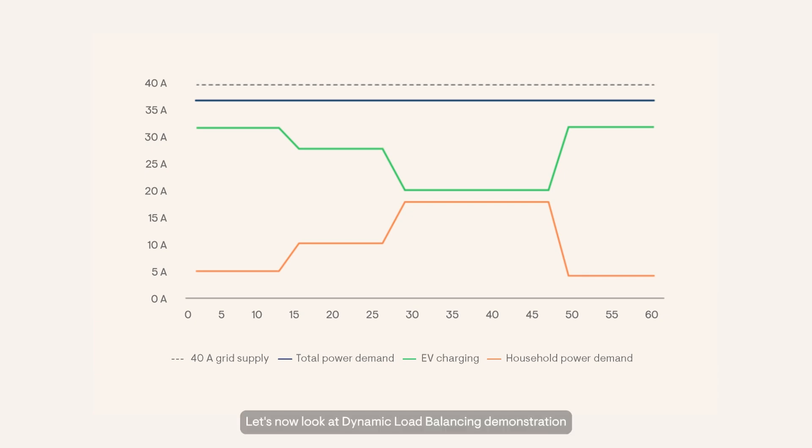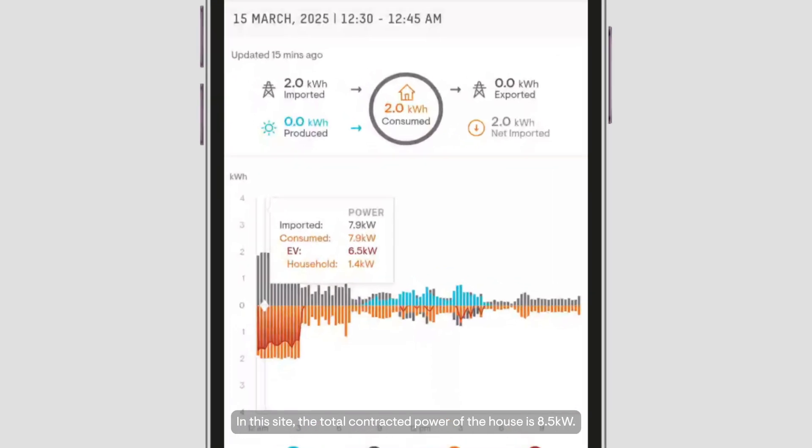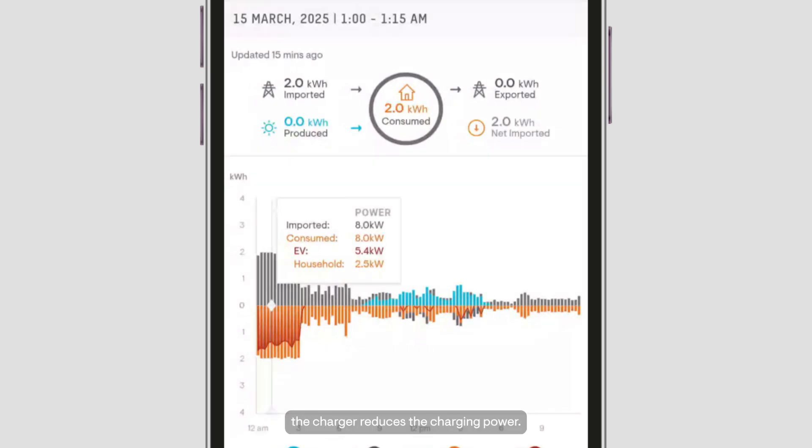Let's now look at a dynamic load balancing demonstration from a home in which IQ EV Charger 2 is installed. In this site, the total contracted power of the house is 8.5 kilowatts. The total imported power of 7.9 kilowatts is being consumed by the EV and the household. At this point, the EV consumes 6.5 kilowatts and the household consumption is 1.4 kilowatts. As household power consumption increases, the charger reduces the charging power.